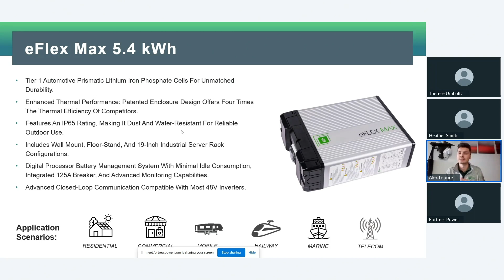The Durarack fits the eFlex Max I just introduced. At the bottom, 4 eFlex Maxes can fit into one bottom cabinet. You can parallel multiple bottom cabinets together if you have larger capacity needs. This is outdoor rated and compatible with 48-volt inverters, with the inverter sitting at the top. Not only is it a pretty neat aesthetic look, in my opinion, but you have the ability to have very easy wire management from the inverter to the battery and between batteries for larger systems. Very easy to parallel multiple inverters and batteries.